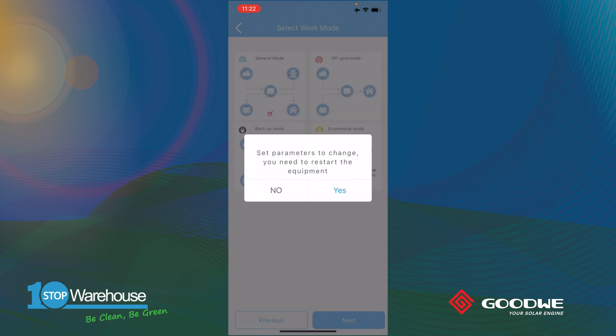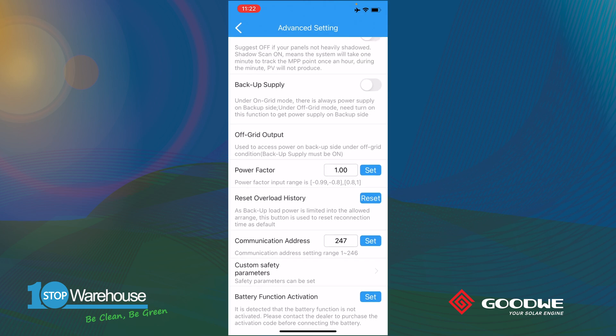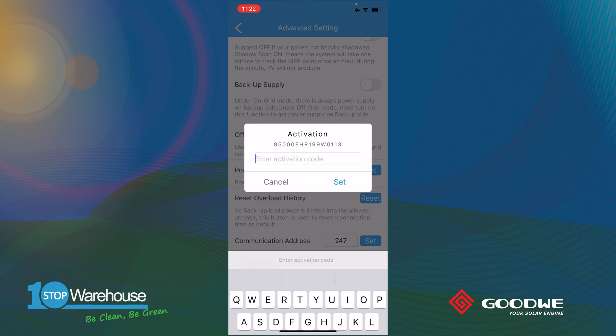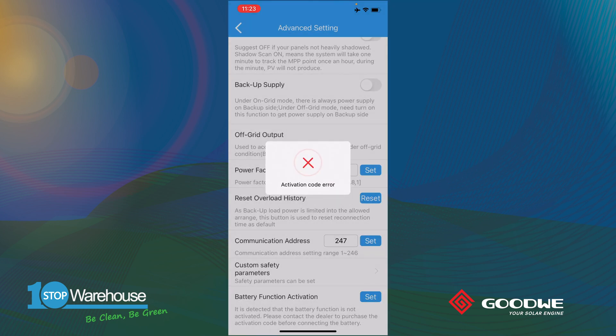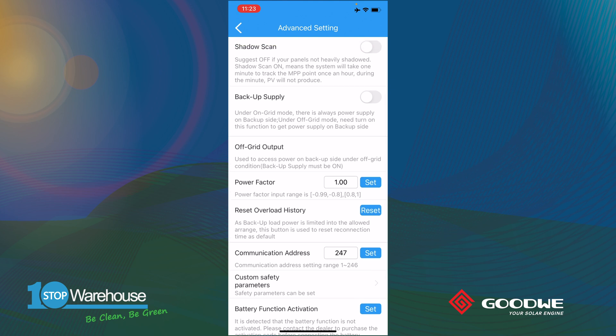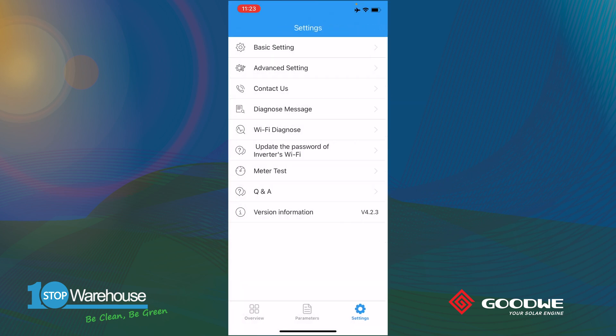Because this is a hybrid ready inverter, you don't need to set up batteries right away. But if you have the battery active code purchased from the wholesale channel, go to Advanced Settings, scroll down to the battery function activation section, press Set, and type in the unique battery active code for your inverter. Press Set to activate the battery function, then go back to Basic Settings to set up the battery configuration.